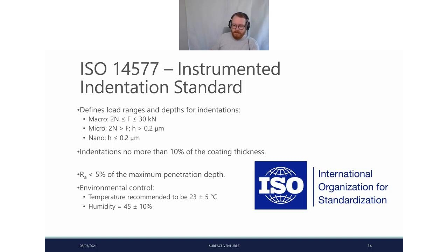Yes. ISO 14577, instrumented indentation standards. This is generally for coatings. So this is what you'd see most often people doing their measurements to. It defines various different ranges here. You've got macro, micro, and nano. Typically it says that indentation should be no more than 10% of the coating thickness. Otherwise, what you're going to see is substrate effects. However, this is just some guidelines.